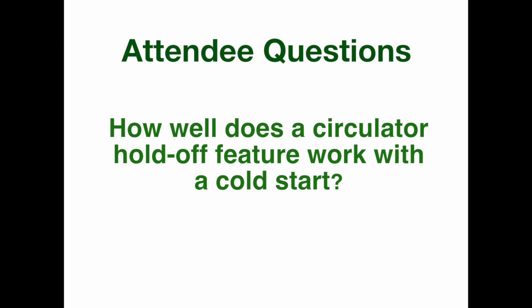One other thing. I think that boiler too, those older Viessmanns, I think they had a fairly high water content. Yeah, it was a high thermal mass content. So it was a big boiler. The other comment I wanted to make on when you were showing the thermostatic mixing valve, the high CV valve that we make, others make a valve like that specifically for boiler protection. They're available with different temperature sensors in them, and you want to be careful with the one you select.